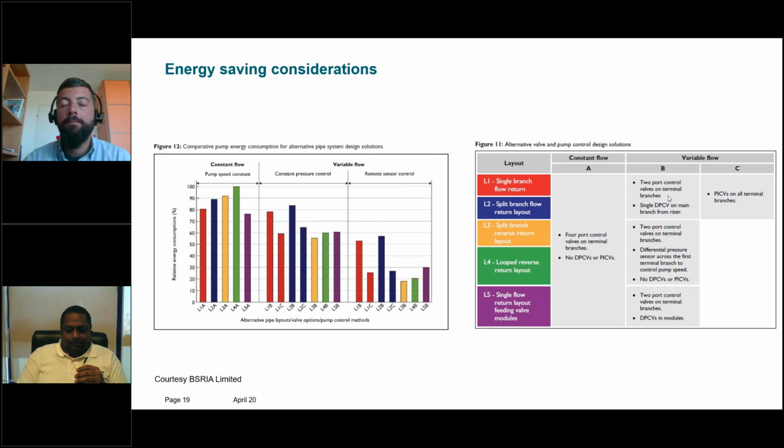So I'll go to the next question, and Jörg, it's for you. The intelligent valve first controls the chilled water flow to the design flow rate, then reduces the flow to achieve the delta T, or does it directly control the delta T first? Under normal conditions, it's controlling first the flow to the design flow rate. And when achieving the design flow rate or a value near to the design flow rate, then it sees a too low delta T, then it will go to the delta T control. As long as delta T is big enough, then it will always go to design flow rate if it gets a 100% set point. Okay, and then the design flow rate is basically what you will preset on the valve. Yes. Okay. Like with the PICV.